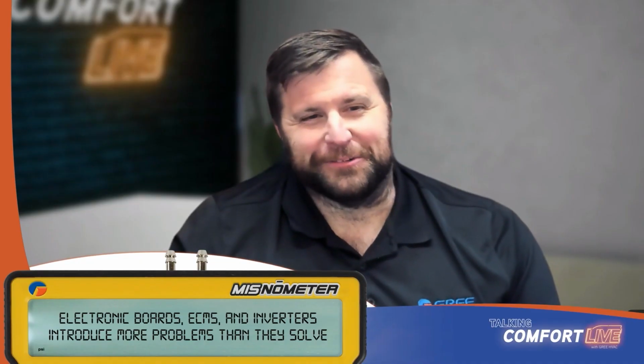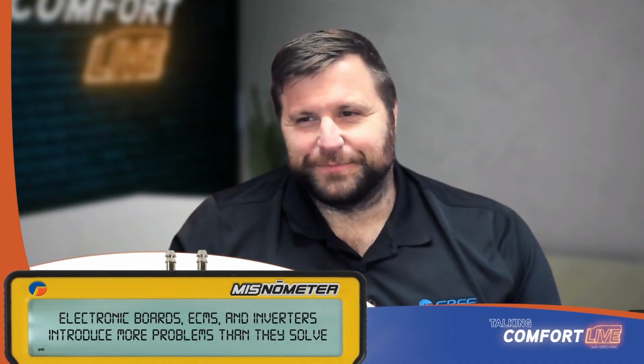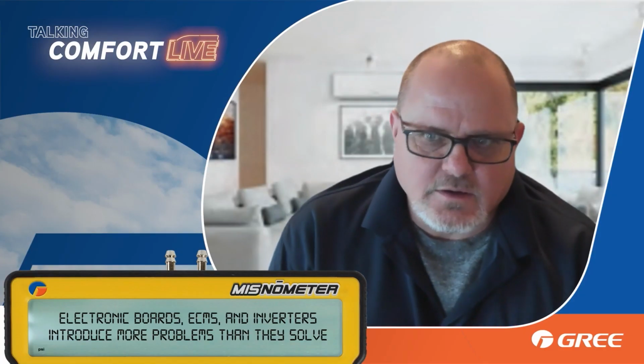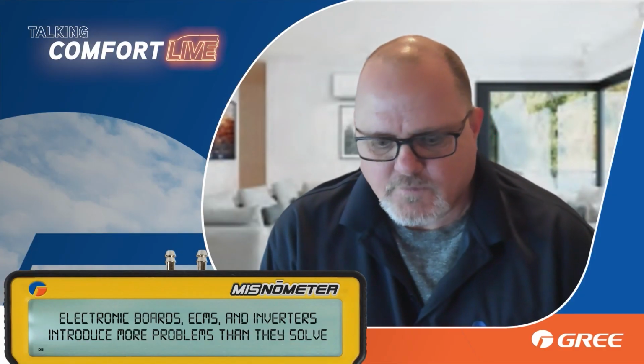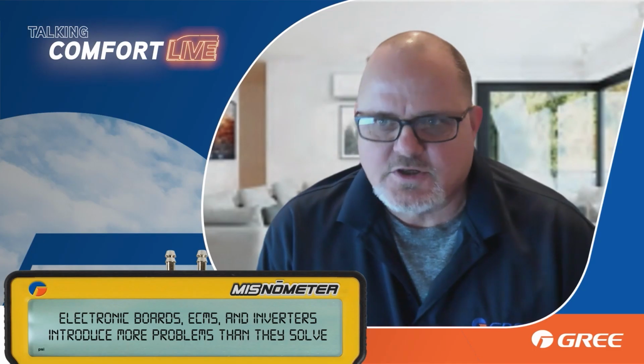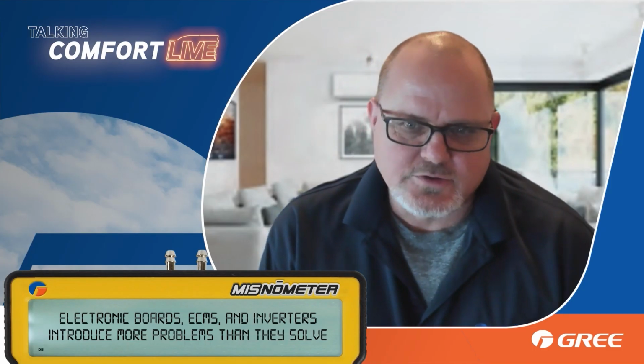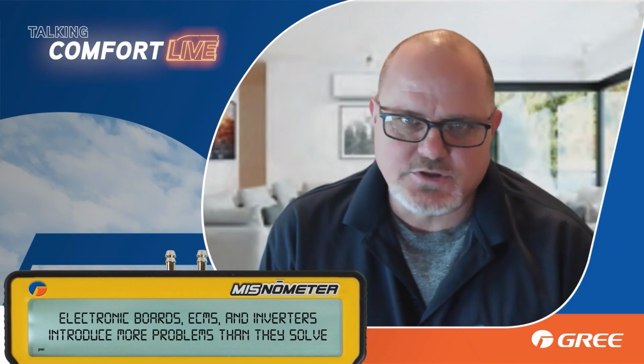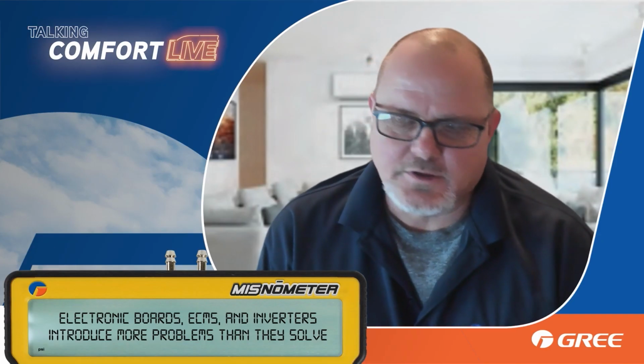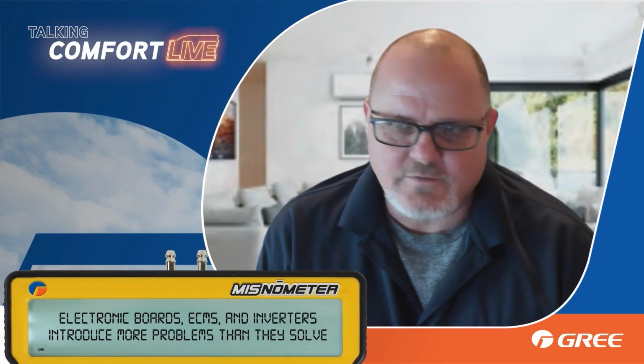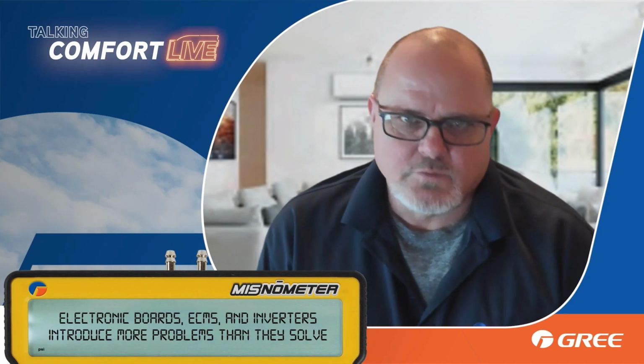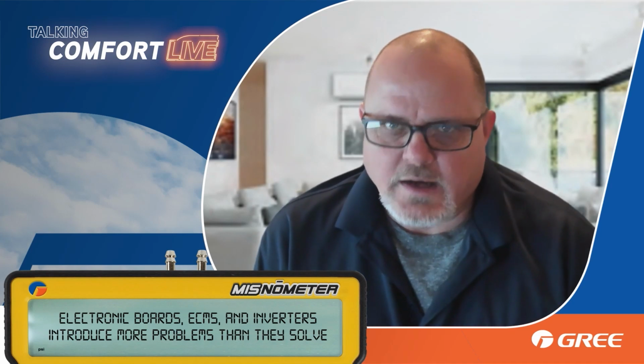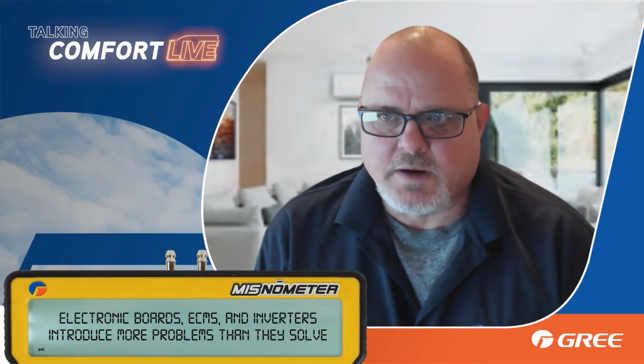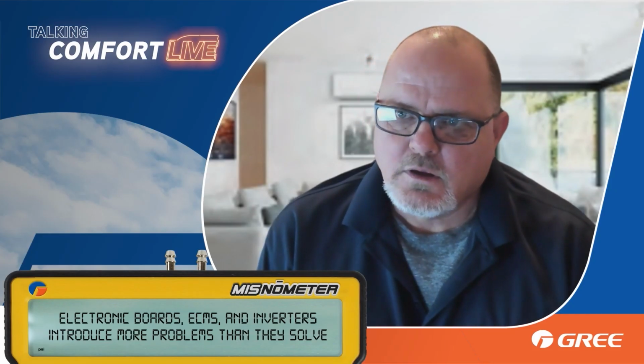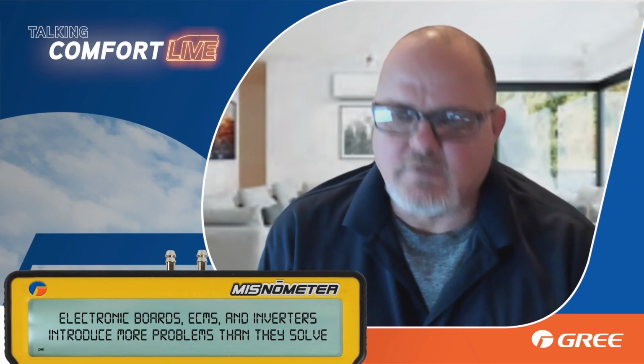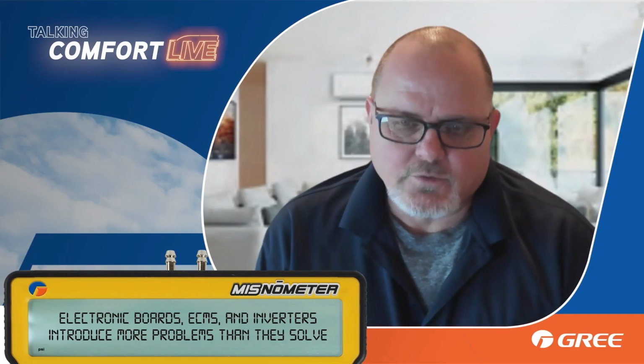Let me say that. When I've talked about that in multiple trainings, I even bring the question up a lot: are the compressors that GREE uses in these machines AC motors or DC motors? They're absolutely a 3-phase AC motor. What they're doing with the inverter driver is creating, from single-phase power, their own 3-phase signal to run that AC motor through that inverter driver.